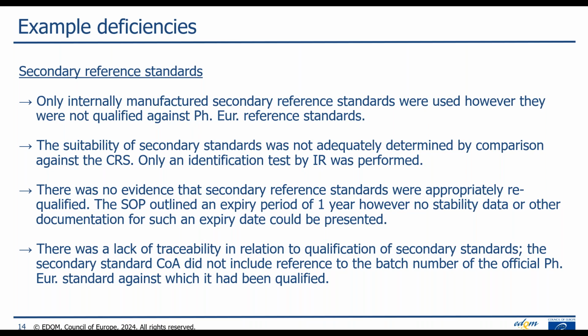Then in terms of the requalification period, we have an example here. There was no evidence that secondary reference standards were appropriately requalified. So the SOP outlined an expiry period of 1 year. However, there was no stability data or other documentation to support such an expiry date.